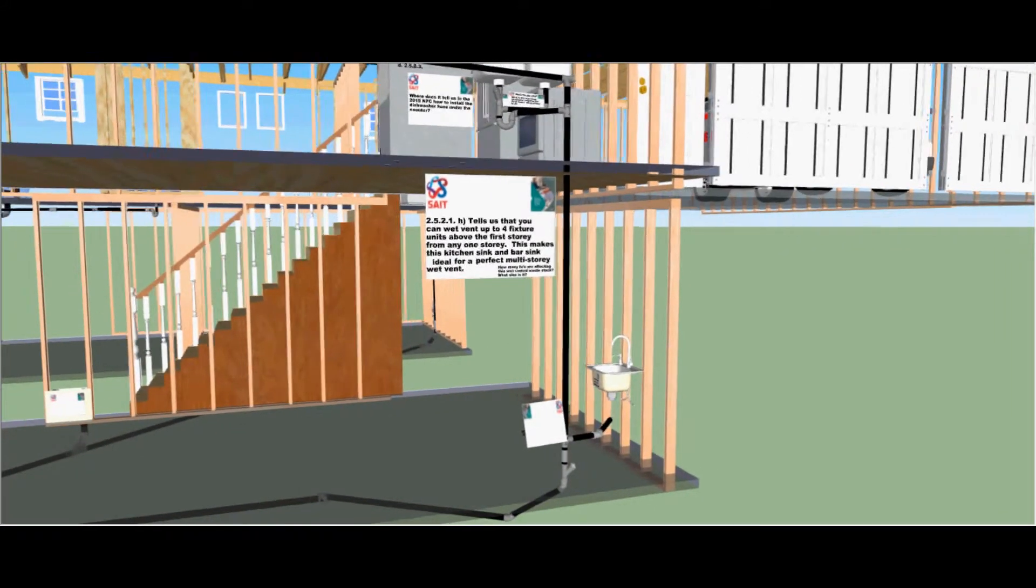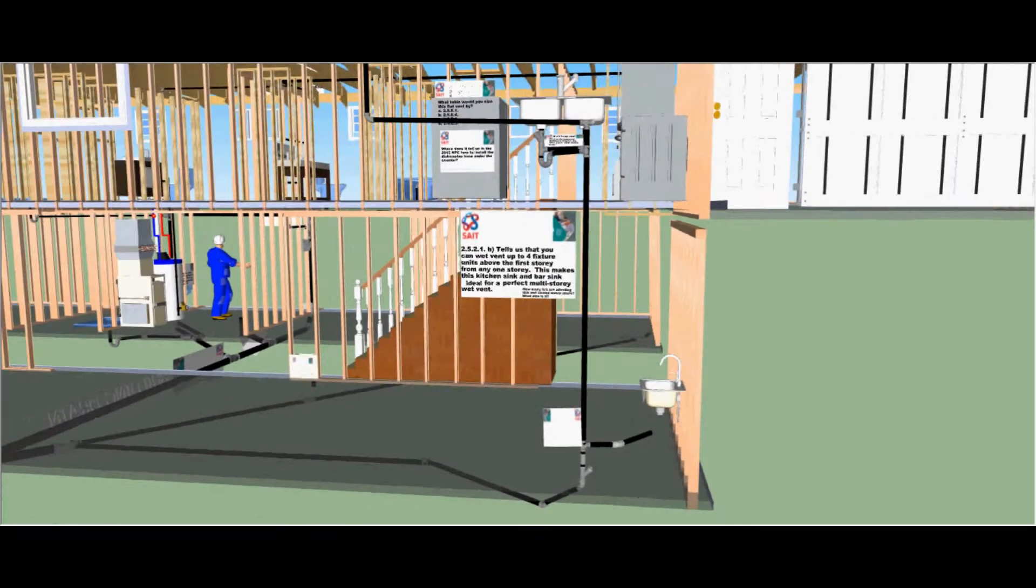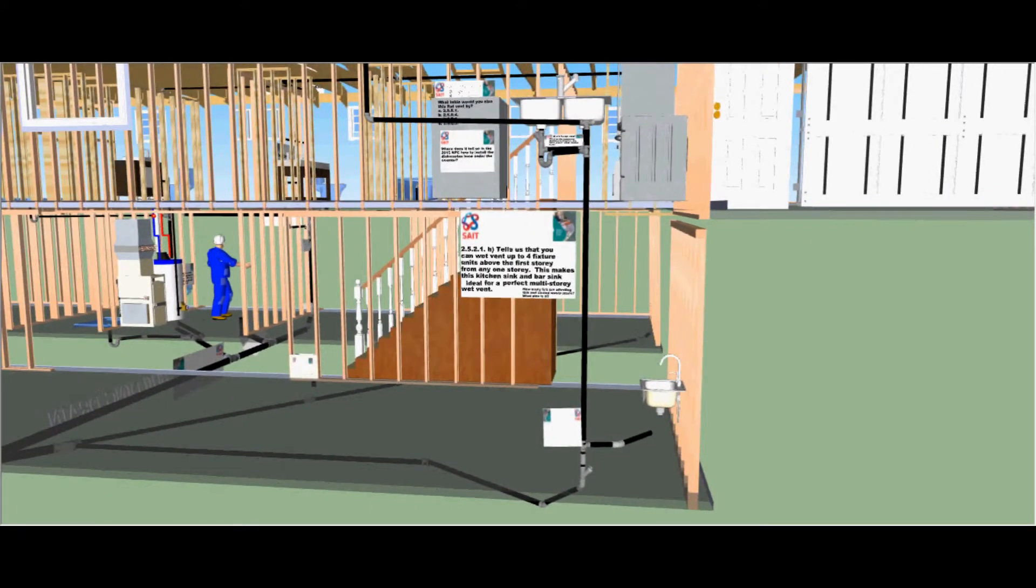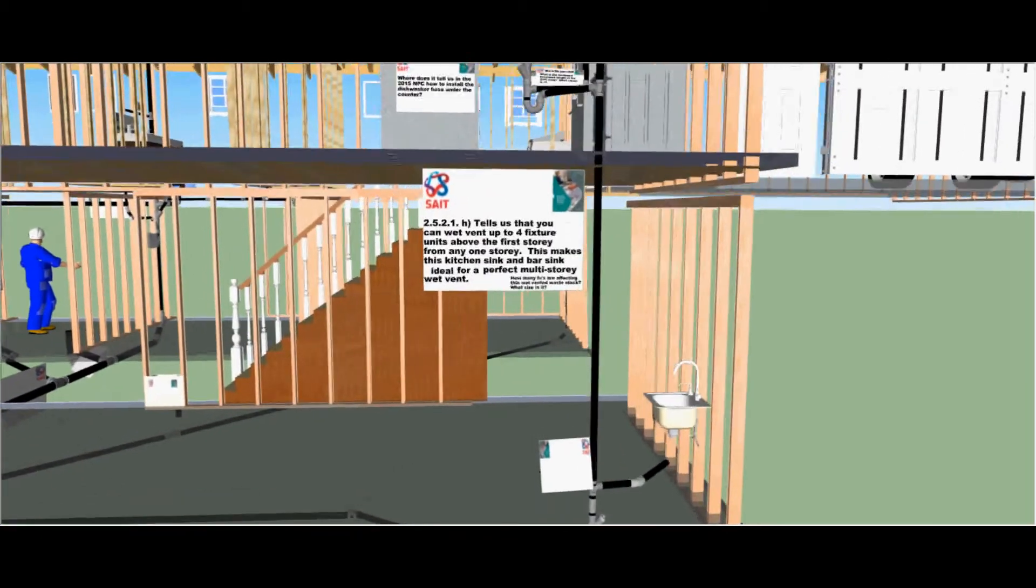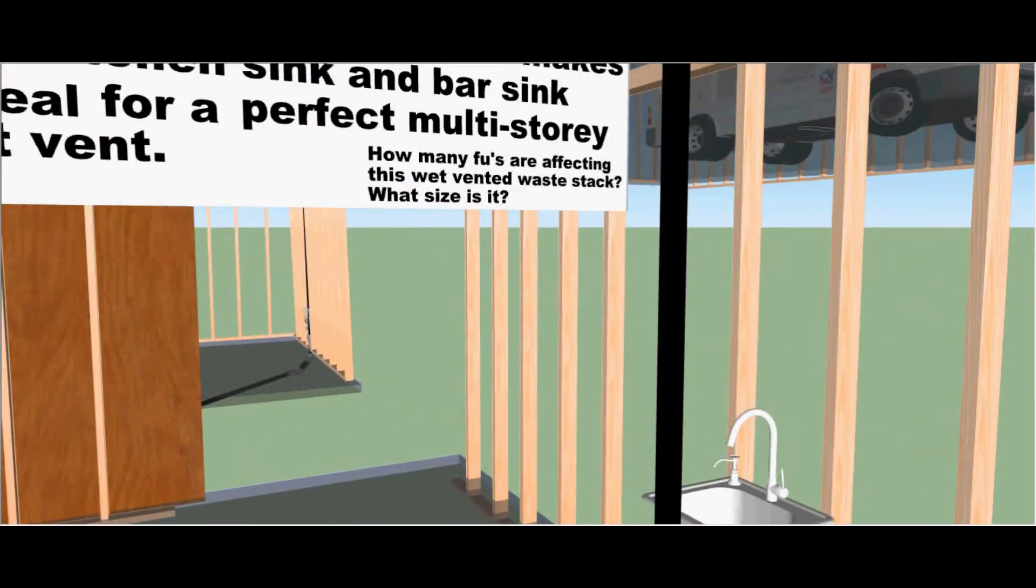Code clause 2.5.2.1 tells us that you can wet vent up to four fixture units above the first storey from any one storey. This makes this kitchen sink and bar sink ideal for a perfect multi-storey wet vent.